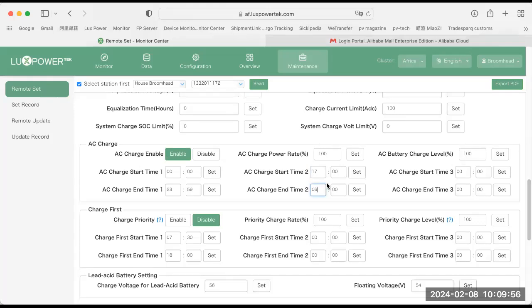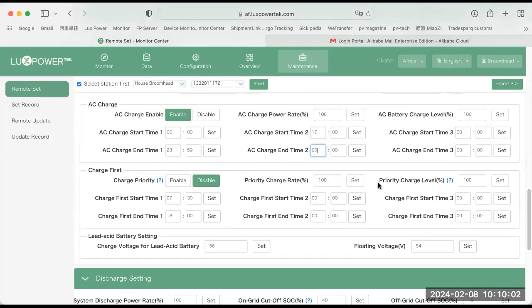This is only on the SNA, on the LXP5. On the LXP12, you can actually set the power in kilowatts, right? And then the charge first, this charge priority, it's got two functions. Number one, it's the charge priority for PV. So here, if I hover over the question mark, you will see that it tells you that if you enable this mode, the solar production will charge the battery first and then supply the load. And if there's surplus, it will feed it into the grid. So typically you would set this during sunlight hours.